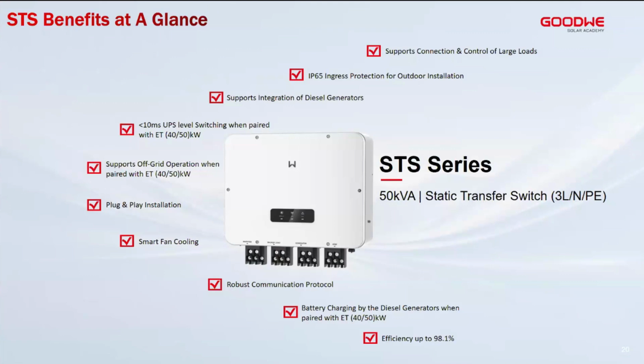Now, this STS is able to connect to different loads. For example, we do have a port called the generator port. That port is not fixed, not really hardwired to only connect to the generator, but you can customize that port to connect to large loads. These large loads can be disconnected or reconnected depending on the state of operation that you would like to set. The product itself is IP65, so it can be installed outdoor.